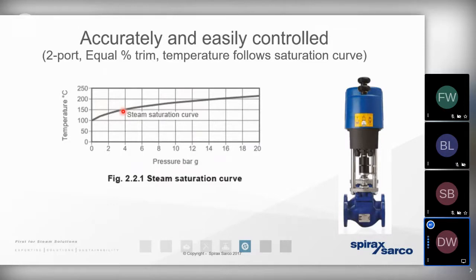So let's compare that to a water-to-water heat exchanger. Well, we know for one, there's far, far less heat energy contained within the water. We also know that whilst we don't pump steam, steam moves in accordance with the pressure drop. We do need to pump the water. And we also know that any heat energy that isn't required by the process, when we're using a water-to-water heat exchanger, we will need to divert that unwanted energy away.